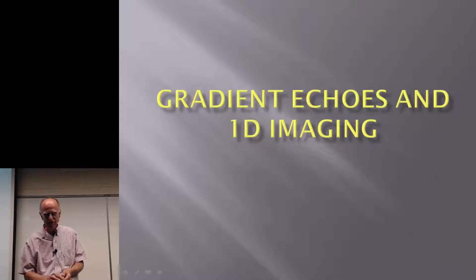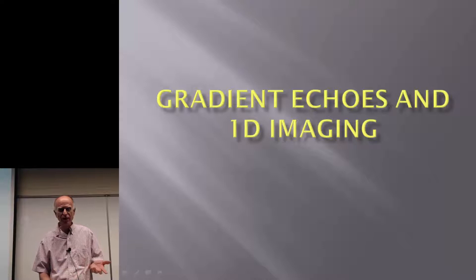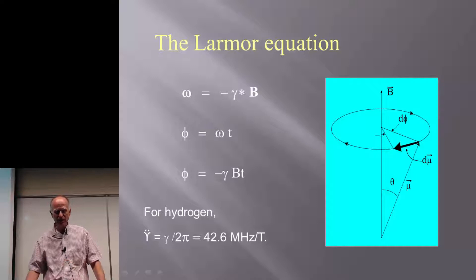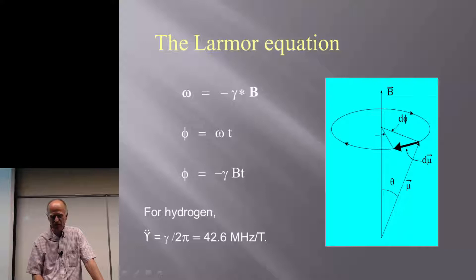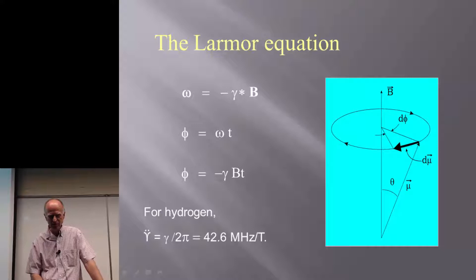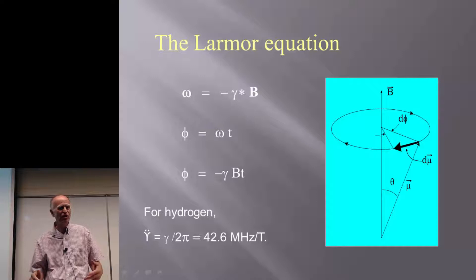So how can we use this to do imaging? We're going to start with a very simple idea: gradient echoes in one-dimensional imaging, just to get the concept across. Let's go back to the Larmor equation and rewrite this. Instead of just writing omega equals minus gamma B, let's replace phase as omega t, and replace omega with gamma B, so phase equals minus gamma B t. The longer you wait, the more phase you have precessed through. Remember that the gyromagnetic ratio gamma-bar — gamma divided by 2 pi — is 42.6 megahertz per tesla. So at 2 tesla, you're at 85.2 megahertz, right up into the FM range.